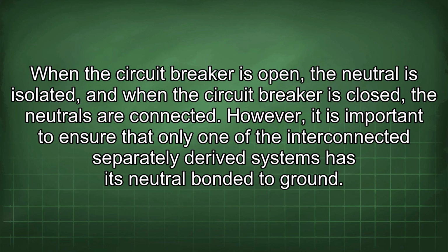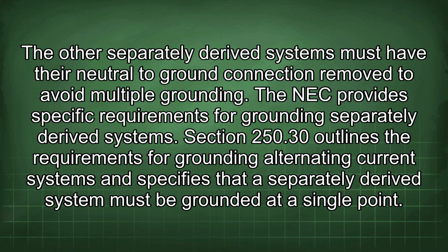When the circuit breaker is open, the neutral is isolated, and when the circuit breaker is closed, the neutrals are connected. However, it is important to ensure that only one of the interconnected separately derived systems has its neutral bonded to ground. The other separately derived systems must have their neutral to ground connection removed to avoid multiple grounding.